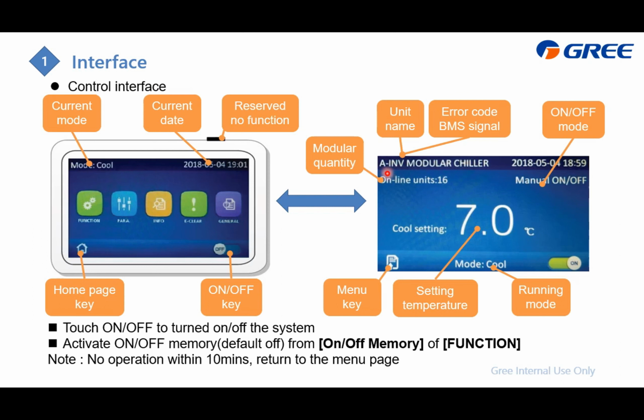Here we display the unit name. This time it is the A series inverter modular chiller, and if there is an error code, it will also display here. Here we display the operating mode. This is the setting temperature. When you press this menu key, it will go to this page. If there is no operation on the controller within 10 minutes, it will go back to the menu page, which is this one.